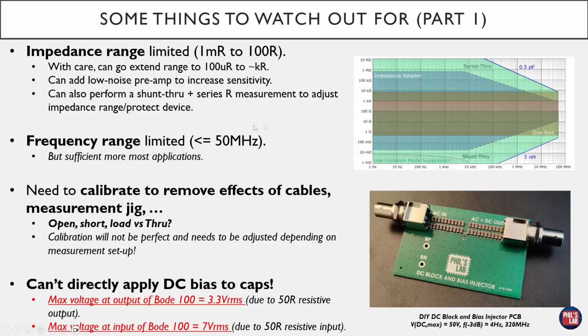The frequency range is also limited, in this particular case of the Bode 100, to less than 50 MHz, which is pretty much sufficient for most power design applications, but if you're characterizing RF components, of course, this might not be sufficient. What is very important that we need to do is calibrate our system to remove the effects of cables, our measurement setup, and more. That is the connectors, the cables. If we're using any bias injectors or DC blocks, they also need to be calibrated out, so we're just focusing on the device under test. We'll see we'll have 2 different calibration techniques, that's open short load or a through measurement. Another thing is we can't directly apply a high DC bias to the measurement.